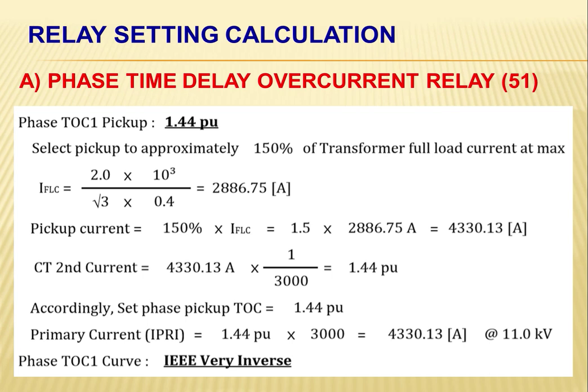First, let's discuss the phase time delay overcurrent relay, or the 51 relay. We're going to check now how we get this phase time overcurrent pickup of 1.44. To arrive at this, we need only to multiply the transformer full load current by 150%. So our transformer full load current on the secondary side is 2886.75 ampere. Then this is multiplied by 1.5, and we have now the pickup current of 4330.13 ampere. Okay, so the TOC pickup will be multiplied also by 1 over the CT ratio, or 1 over 3000.